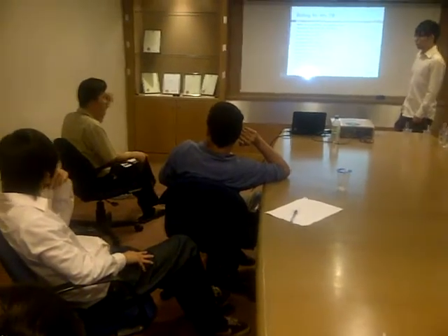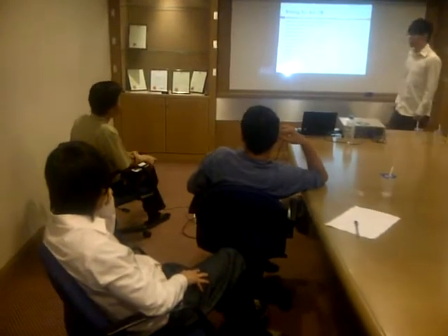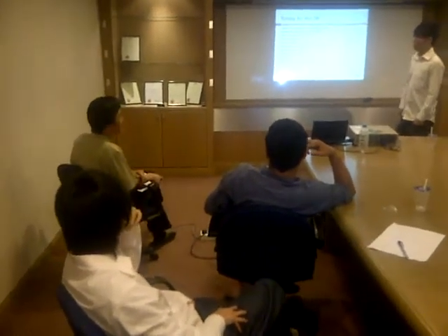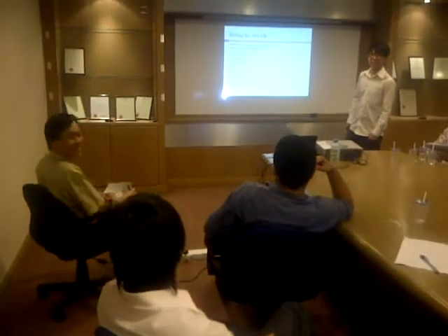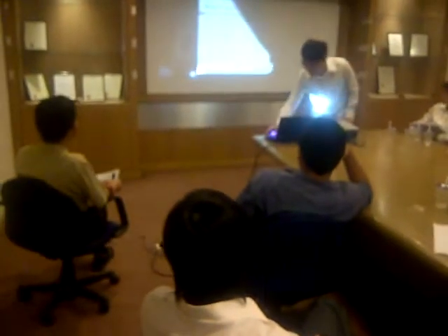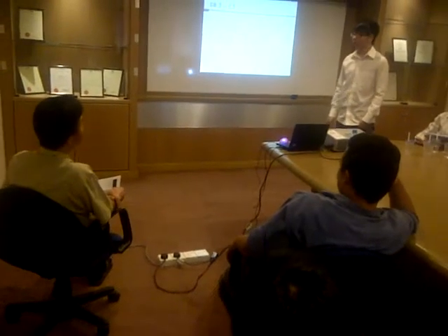This is very important. Okay. So I look at the 35, I think, just look at the amp rating, I think it's low. Under specs. Undersize again. Yeah, under specs. It's okay, no more. Anyway, when you make a mistake, only then you learn. If everything is perfect, you won't learn. But from here, after you learn, next exercise you will become better. But you must know how to read the table. You must know how to apply the correction factor.